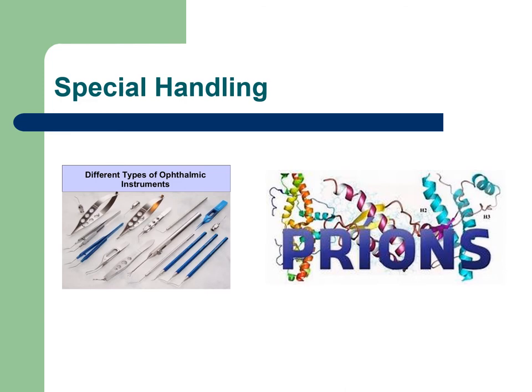So if we can use disposable cannulas instead, that's the best. Anything with a lumen needs to be flushed and brushed. In decon, they'll flush and brush it, then put it in the ultrasonic, and inspect it closely for any residue before they sterilize it.